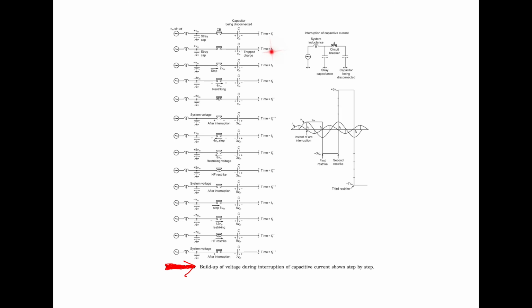Now, at the instant T2, which occurs half a cycle later, after 10 milliseconds, the system voltage attains the value of minus Vm. At this instant, the contact gap is therefore stressed to the voltage of 2 Vm, and this can be taken as an application of a step voltage of 2 Vm, and the peak restriking voltage is 2 times 2 Vm, as we have discussed. So the peak restriking voltage is equal to 2 into 2 Vm, which is equal to 4 Vm.